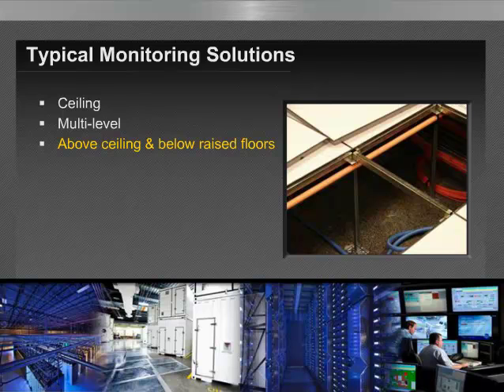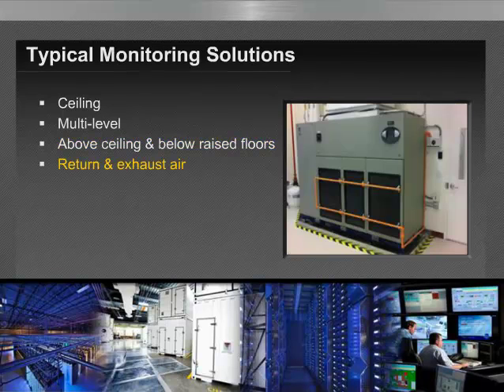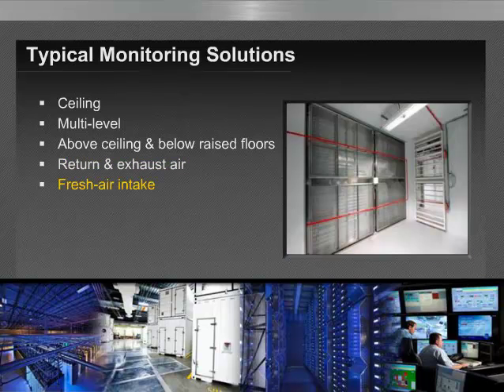Return air, as we've talked about, the idea of monitoring various points such as return air paths, transfer grills, even the supply side of HVAC systems. And as well, the idea of monitoring fresh air intakes. So we're monitoring the quality of the air coming into the space to make decisions about that air, which may be smoke-laden, contaminated, and we don't want to bring that environment into the facility. So we're using these types of technologies that can provide more analytics, higher sensitivity, and potential for detecting contaminants coming into the space to make logical decisions with the building management system for either recirculation mode or economization mode under certain conditions. There's a growing trend.